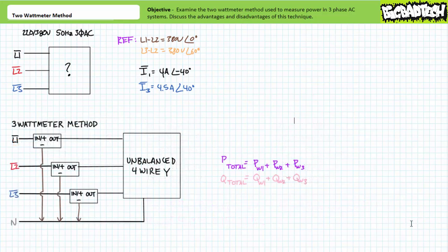If, however, a fourth wire protrudes from the box, we're most likely dealing with an unbalanced four-wire Y configuration. Given the degree of imbalance observed in the line currents, there will undoubtedly exist imbalance current in the neutral line. As such, the two-wattmeter method would be blind to the imbalance and we would need to resort to a more expensive and time-consuming three-wattmeter method. This being said, implementing the three-wattmeter method for an unbalanced four-wire Y configuration is relatively easy because all the test points are externally accessible, in contrast to the other configurations.